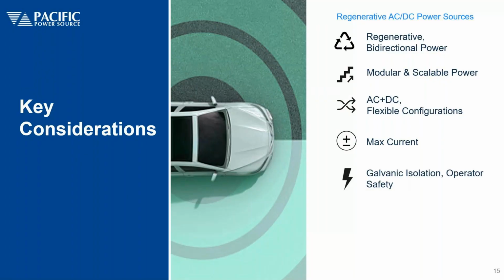Another aspect has to do with safety, operator safety. In this case, is the grid simulator output isolated from the grid that feeds it? So having isolation, galvanic isolation in between is an important issue. It allows you to float your EUT away from ground if needed, without having to worry about operator safety issues, and that can definitely be an important decision-making consideration.